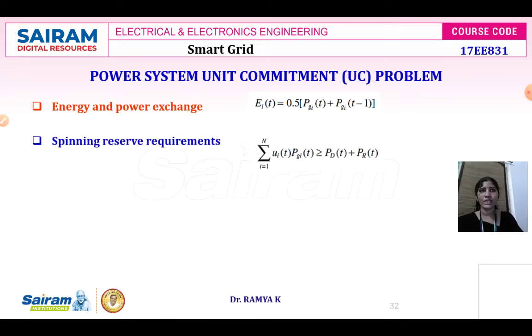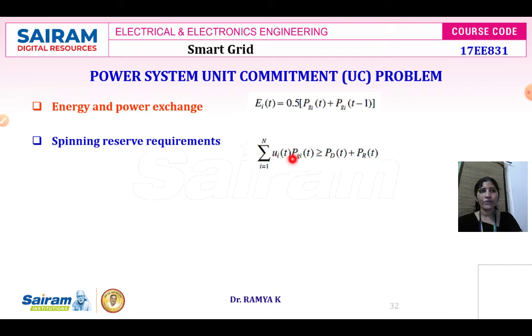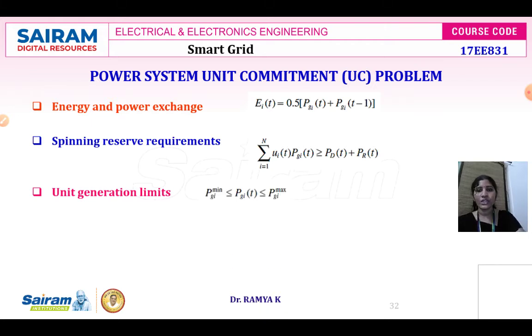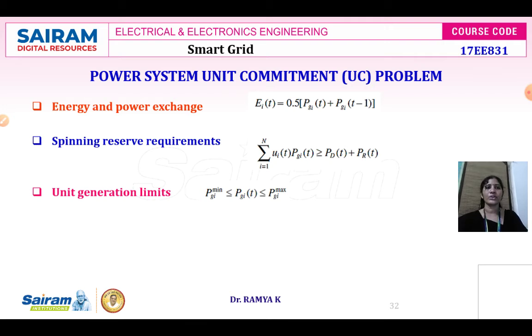The spinning reserve requirement is: summation i equals 1 to N of ui(t) times PGi(t) greater than or equal to Pd(t) plus Pr(t), where Pd(t) is power demand and Pr(t) is spinning reserve required at time t. The unit generation limit constraint specifies that PGi minimum must be less than or equal to PGi(t), which must be less than or equal to PGi maximum, identifying minimum and maximum power output for each unit.